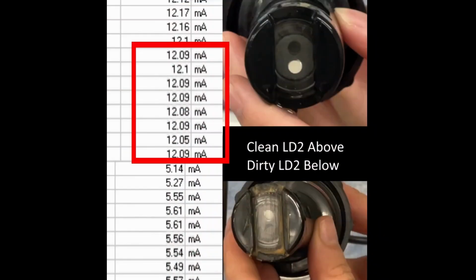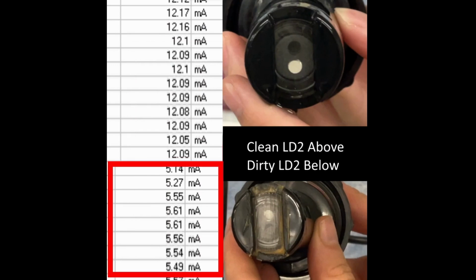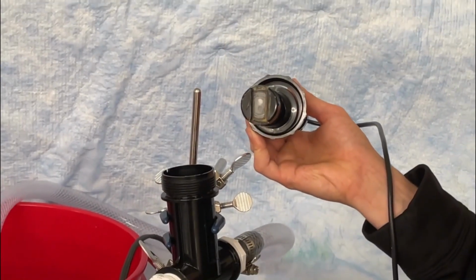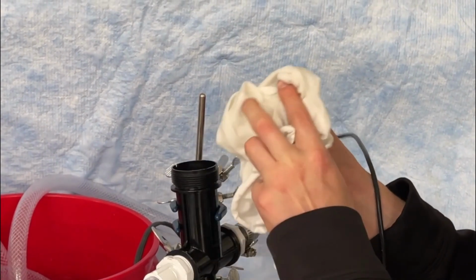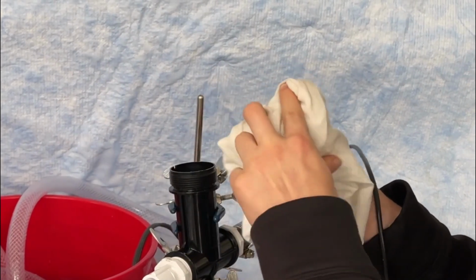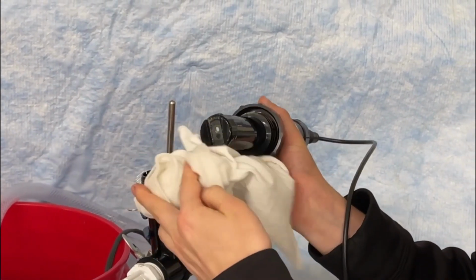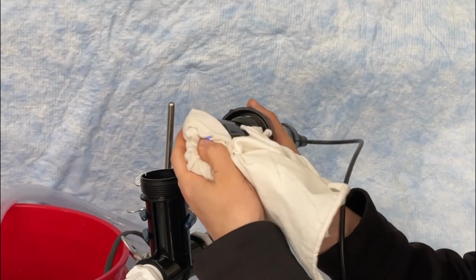If we do some comparison between the first clean LD2, it is reading as 12 milliamps in 100 ppb PTSA. Transitioning over to our second LD2 that was dirty, it is reading as 5 milliamps in 100 ppb PTSA. So to clean the probe, we will first try using a clean rag with warm soapy water. Wipe the optical head until it looks clean, and then reinstall the probe.